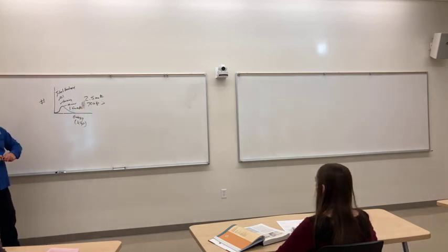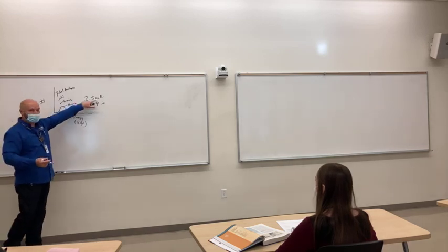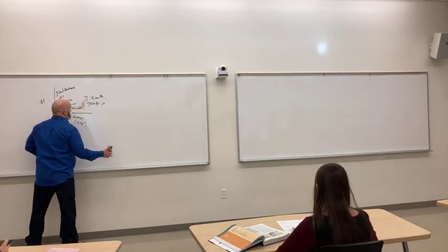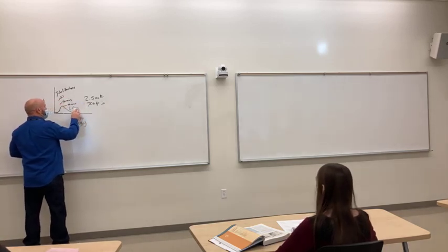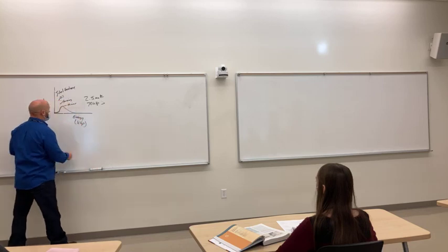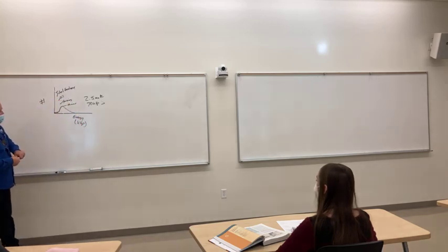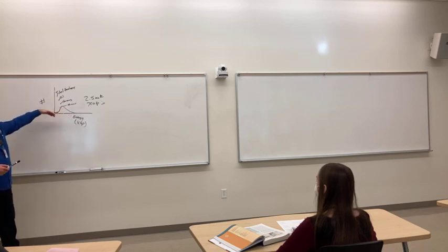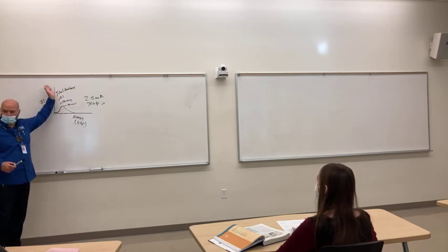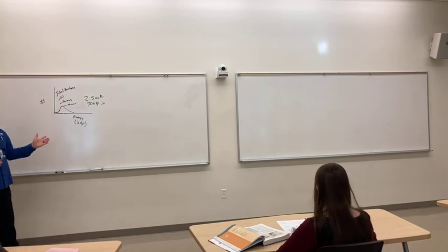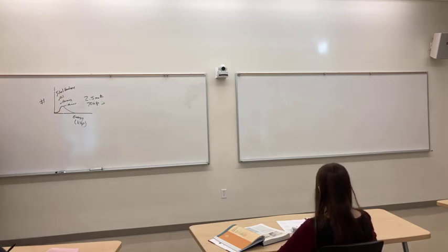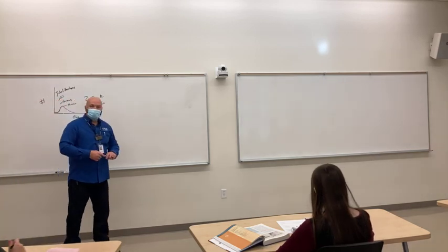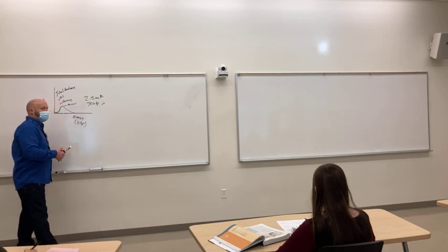More. We need more. Because legally we have to get to this point before we can make the exposure on a patient. So we have to get to 2.5 millimeters of aluminum, and therefore our bremsstrahlung spectrum becomes more and more filtered, so that it takes on this elongated bell curve appearance as opposed to that, not really a straight line, that slope that we had before, okay? So we're going to start with filtration in things that affect the bremsstrahlung spectrum.